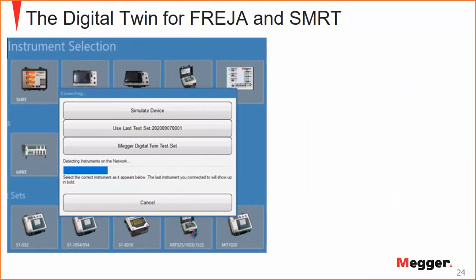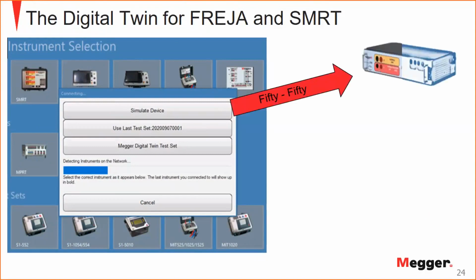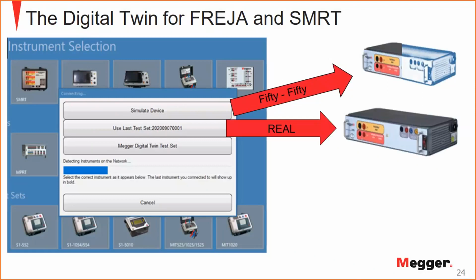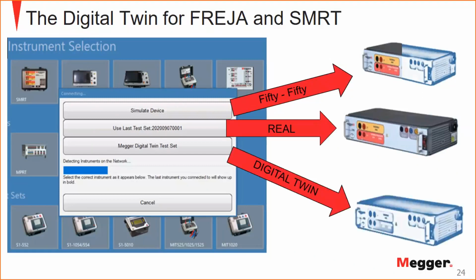The digital twin for a Freya, or in Sweden we say Freya, in English we should say Freja, and SMRT test sets, it's working like that. It's based on RTMS software, where you know that we had a sort of simulation. It's not a digital twin, but that was the fact that triggered all of this project. The fact that we had something called simulate device triggered the interest, and we then developed the digital twin. So that, if you know what it is, it's not a digital twin. It's 50-50, let's say. You can connect to a real test set, or you connect to a Megger digital twin test set.